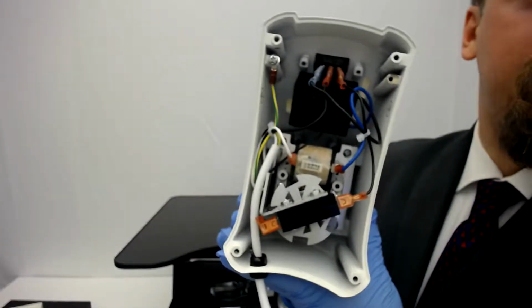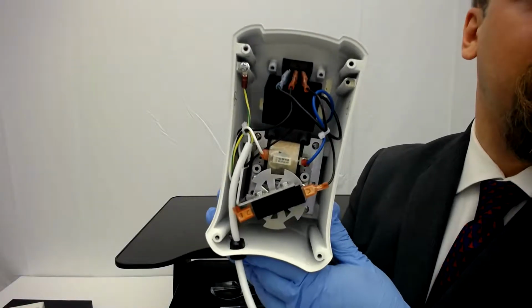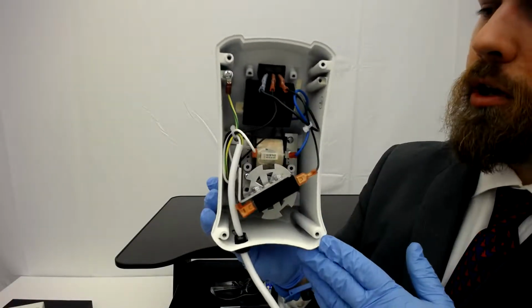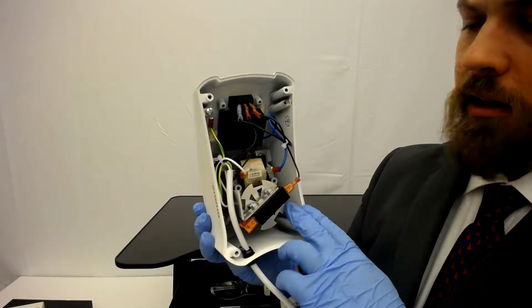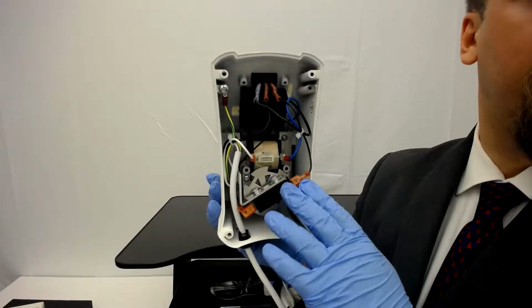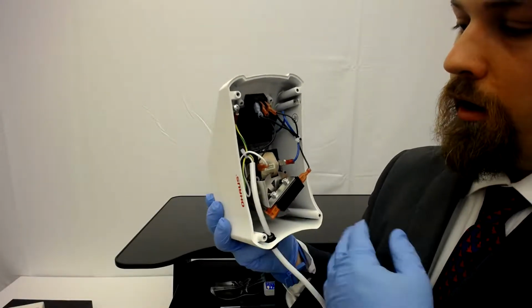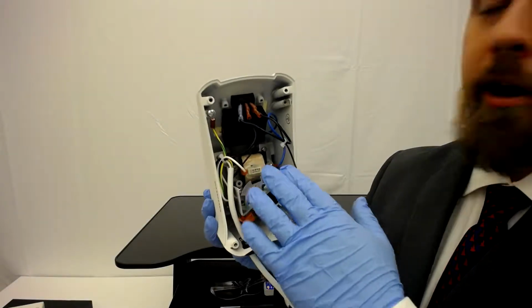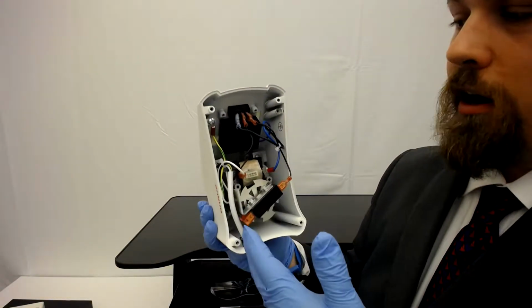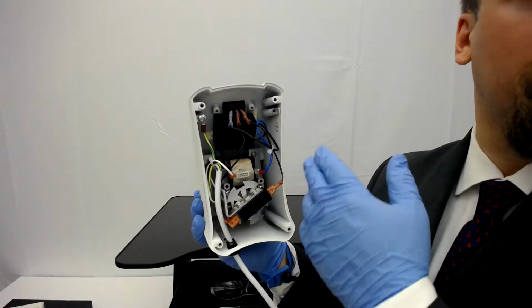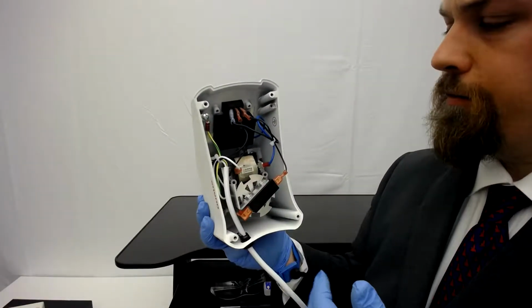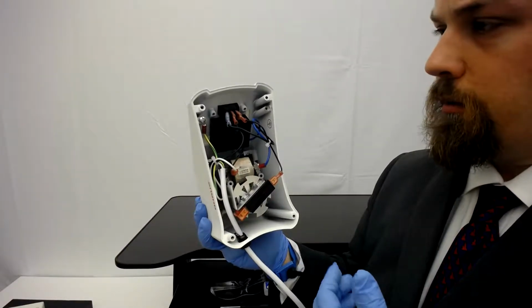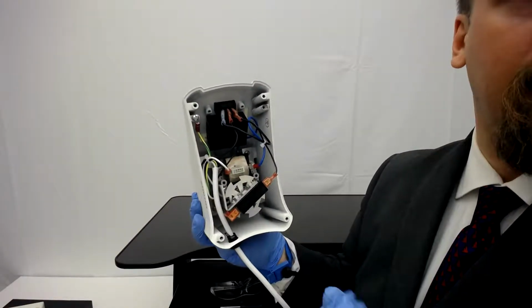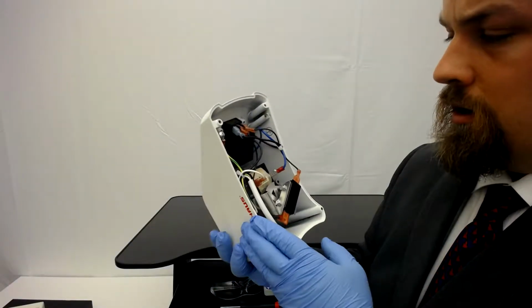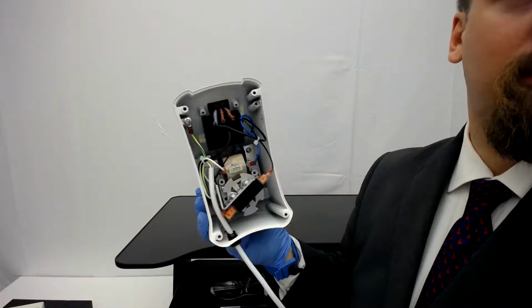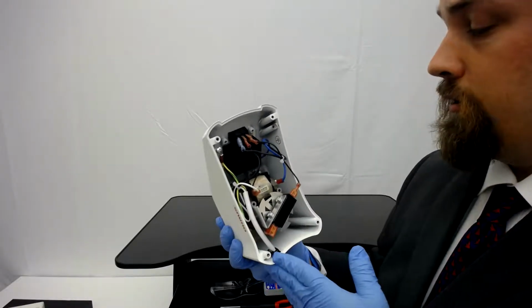So as you're doing the quality check, the first thing you do after you open really any of these units is look at the wiring. Make sure there's nothing coming into contact with the motor, that there's no tears or breaks in any of the insulation, and that all the wire routing is correct in the unit, that all the wire ties are in place. That's a fairly important thing to do on every unit that we open up, look at, and calibrate before moving on. Also, never hurts to take a picture of this and document it.